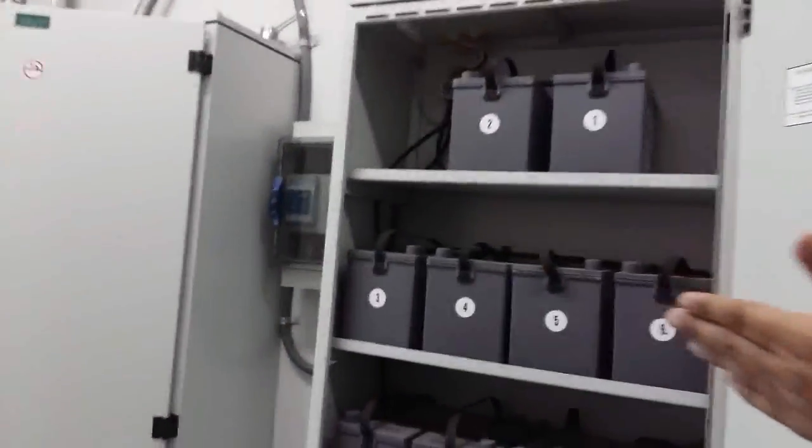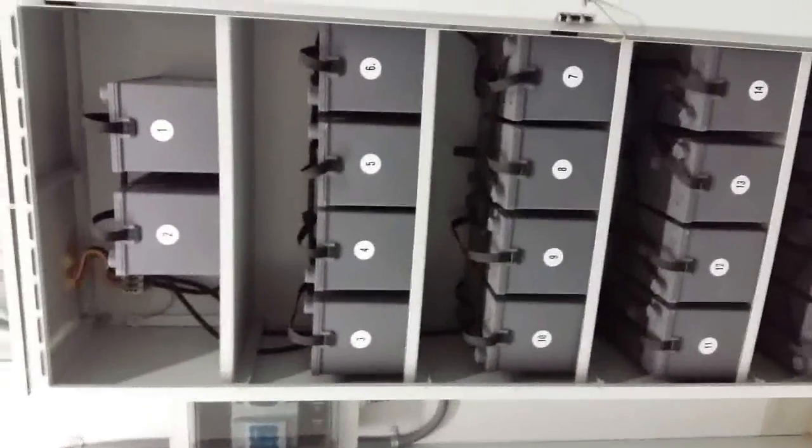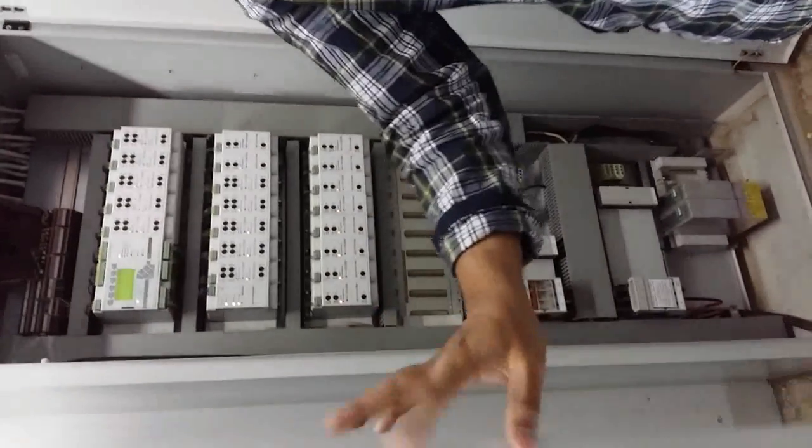What is the ampere hour for one battery cabinet? For example, 50 ampere hour. So if we add 50 plus 50, it will give 100 ampere hour, but keeping the voltage constant at 216 volt. So we are receiving 100 ampere hour with 216 volt DC voltage. Is there anything you want to say on this, Mr. Muhammad? What is this thing? You can speak about this.